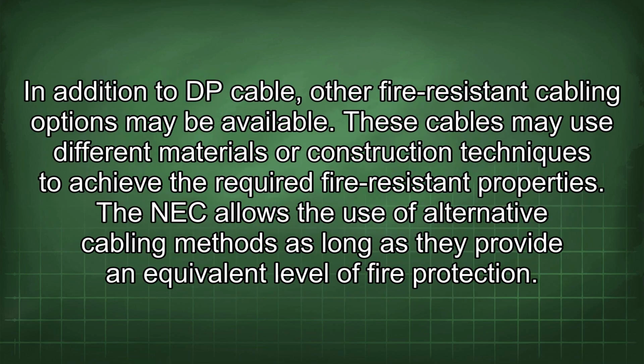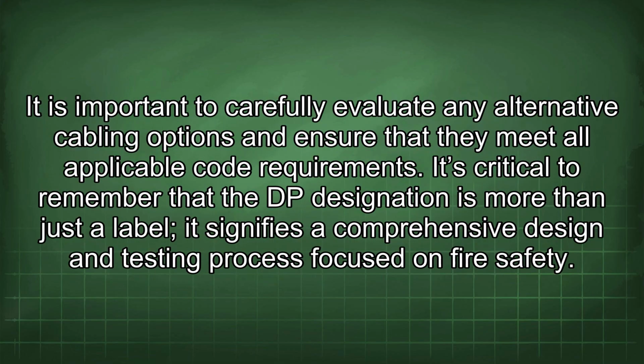In addition to DP cable, other fire-resistant cabling options may be available. These cables may use different materials or construction techniques to achieve the required fire-resistant properties. The NEC allows the use of alternative cabling methods as long as they provide an equivalent level of fire protection. It is important to carefully evaluate any alternative cabling options and ensure that they meet all applicable code requirements.